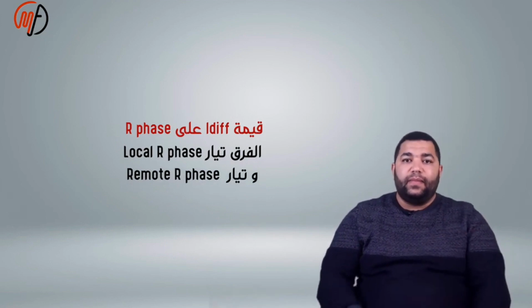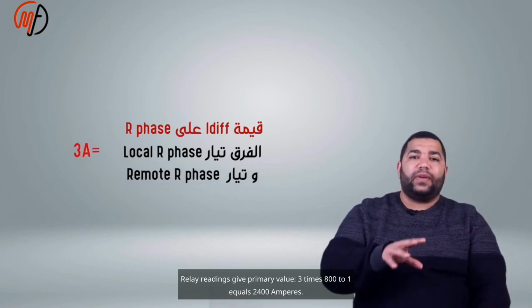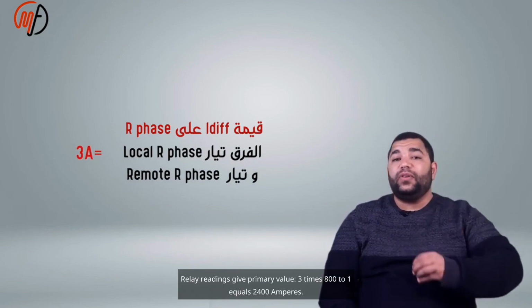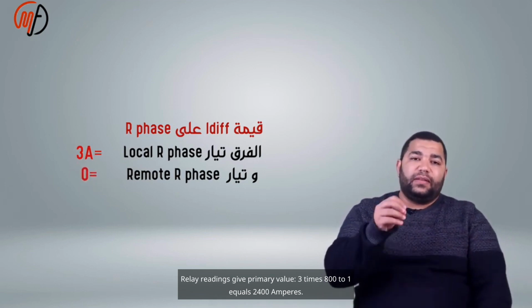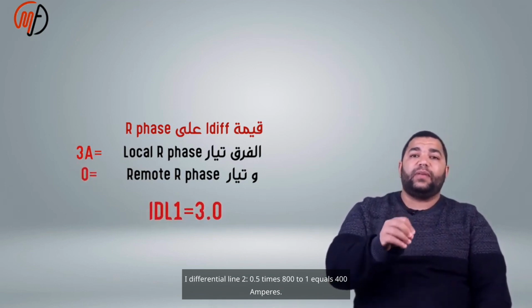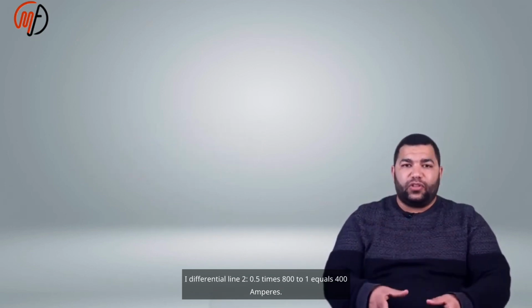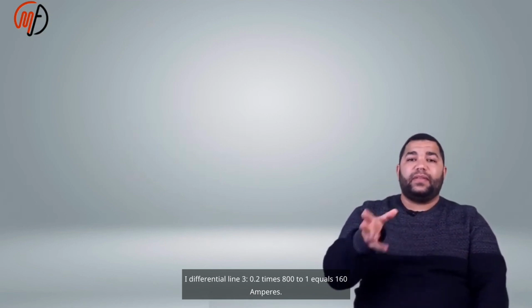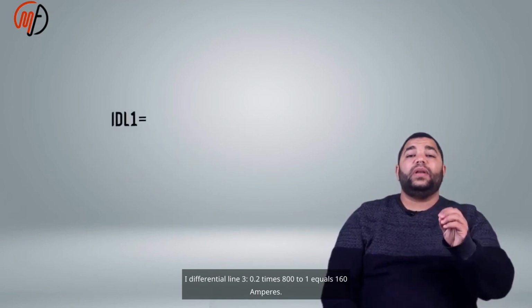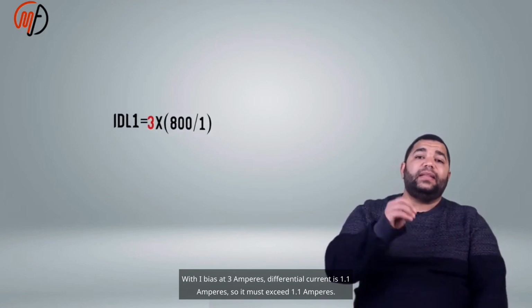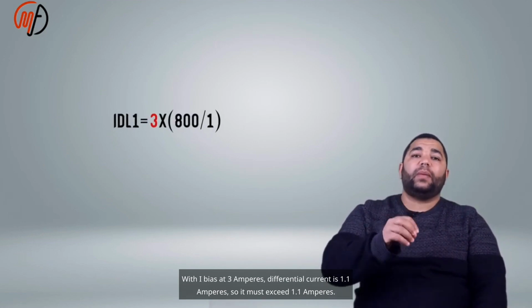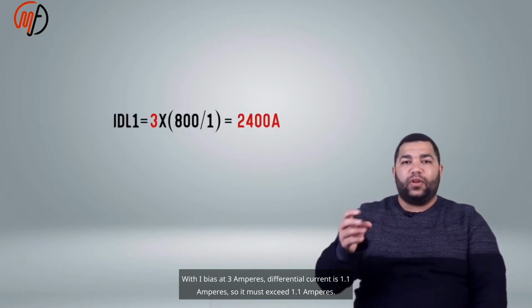And the value equals 3 amperes. Relay readings give the primary value: 3 times 800 to 1 equals 2400 amperes. I differential line 2, 0.5 times 800 to 1, equals 400 amperes. I differential line 3, 0.2 times 800 to 1, equals 160 amperes. With I bias at 3 amperes, the differential current is 1.1 amperes, so it must exceed 1.1 amperes.